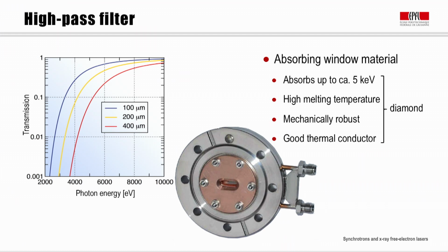Thin, artificially grown diamond windows are commercially available and can be brazed onto a water-cooled vacuum flange, as shown here. Obviously, this high-pass filter is not used for beamlines operating in the tender or soft X-ray regime.